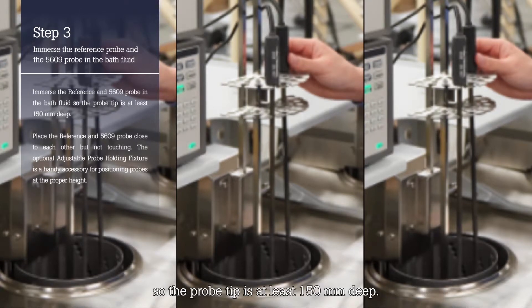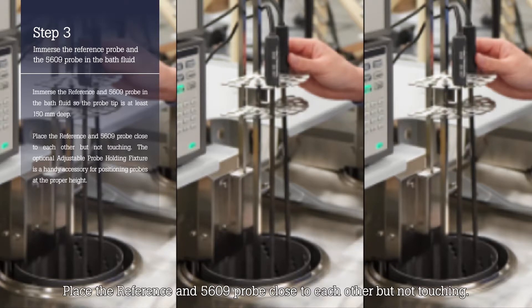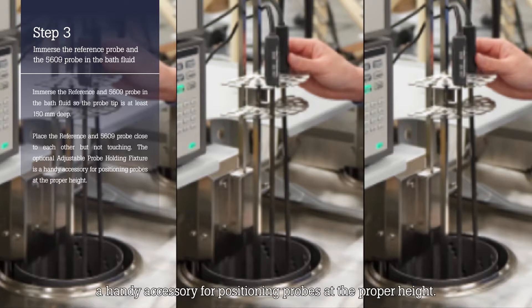Step 3. Immerse the reference and 5609 probe in the bath fluid so the probe tip is at least 150 millimeters deep. Place the reference and 5609 probe close to each other but not touching. The optional adjustable probe holding fixture is a handy accessory for positioning probes at the proper height.